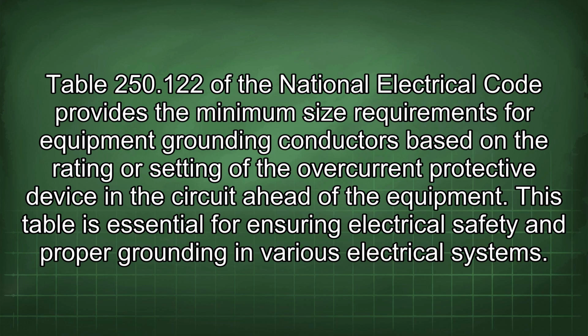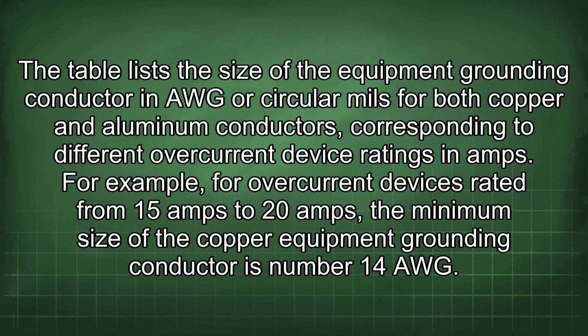Table 250.122 of the National Electrical Code provides the minimum size requirements for equipment grounding conductors based on the rating or setting of the overcurrent protective device in the circuit ahead of the equipment. This table is essential for ensuring electrical safety and proper grounding in various electrical systems. The table lists the size of the equipment grounding conductor in AWG or circular mils for both copper and aluminum conductors, corresponding to different overcurrent device ratings in amps.